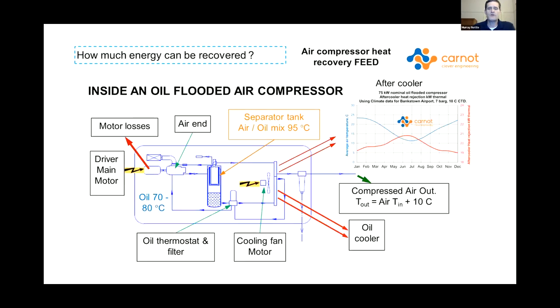So what's actually inside an air compressor and where does all the heat flow? This is a generic drawing of an air compressor. The air comes in at the top left there, goes into the air end, which is a compression module, gets compressed, and oil gets added to it. As we've heard with the refrigeration screw compressors, they inject oil there, same with an air compressor for most of them. The hot air-oil mixture goes into what's called the separator tank, and the oil drops out and the air goes out to the after cooler.